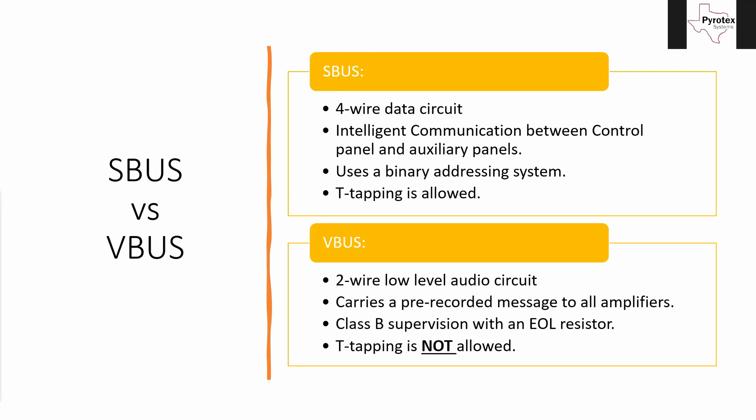The VBUS is Class B supervised, just like a speaker circuit or a NAC circuit. There's an end-of-line resistor at the end, and that's the only way the panel knows the circuit is complete — by seeing that resistor. It's not actually talking to each of those panels; it's just sending an output and supervising for that resistor. Because of that, there is no T-tapping allowed on the VBUS.